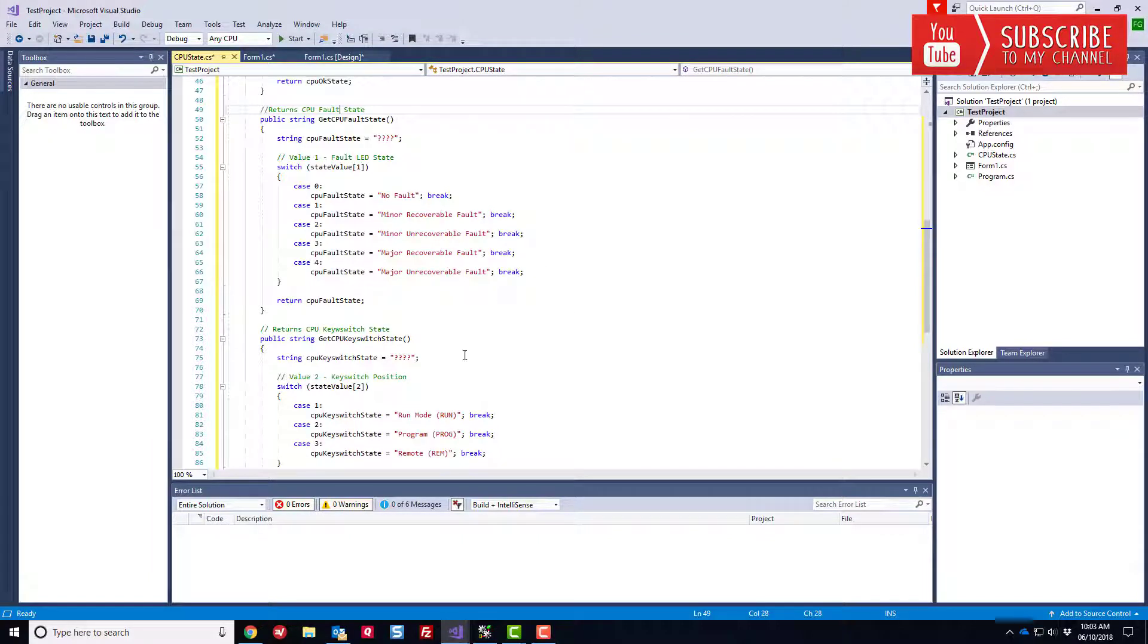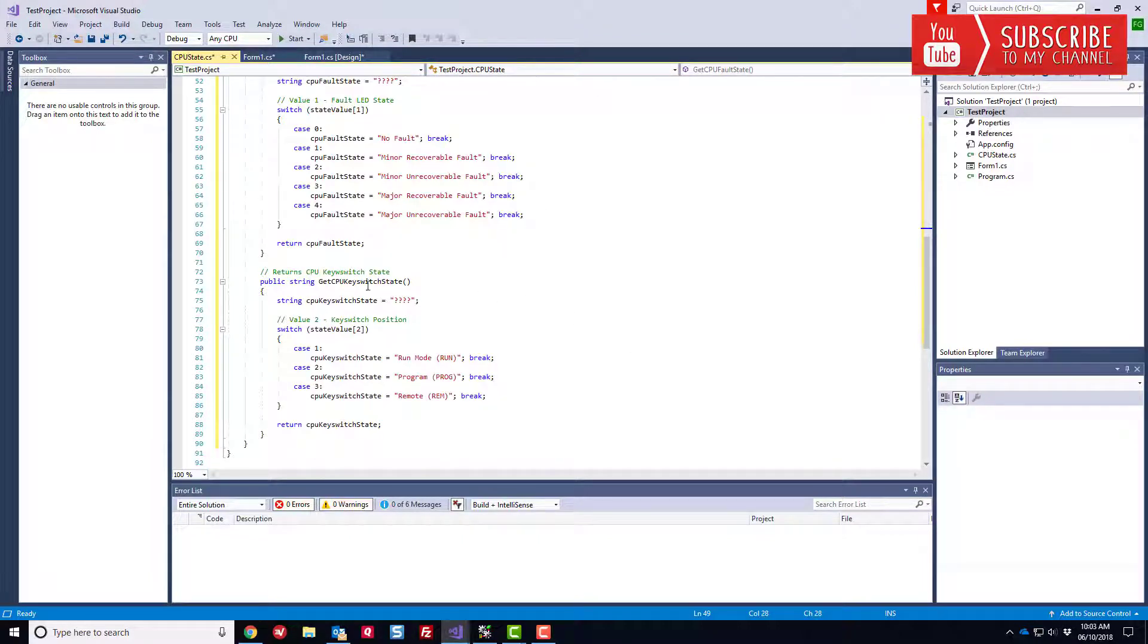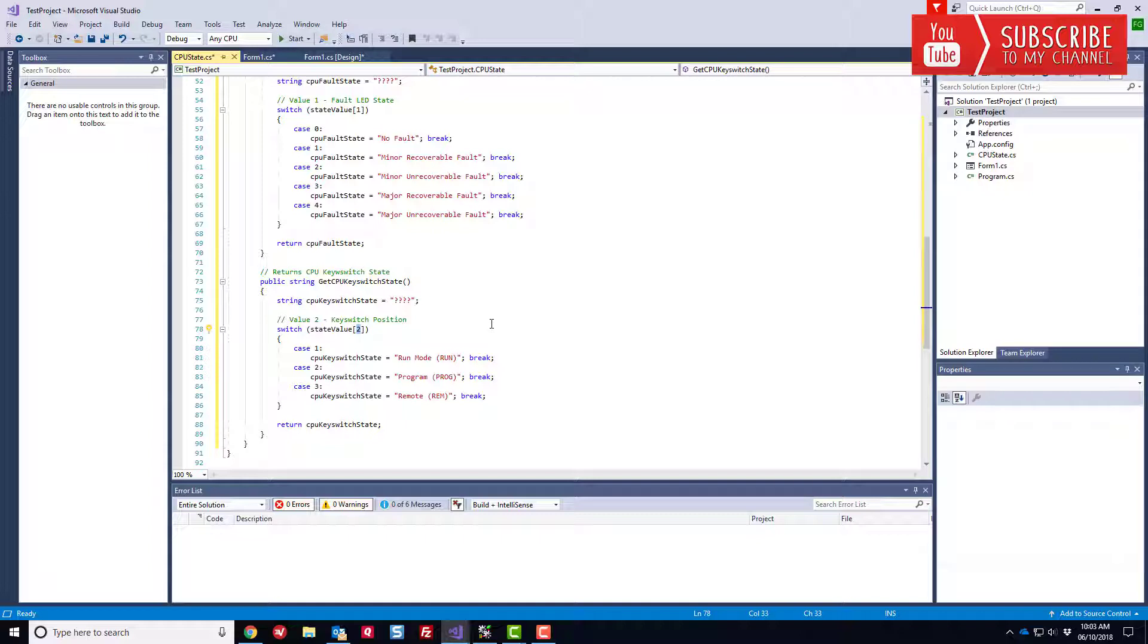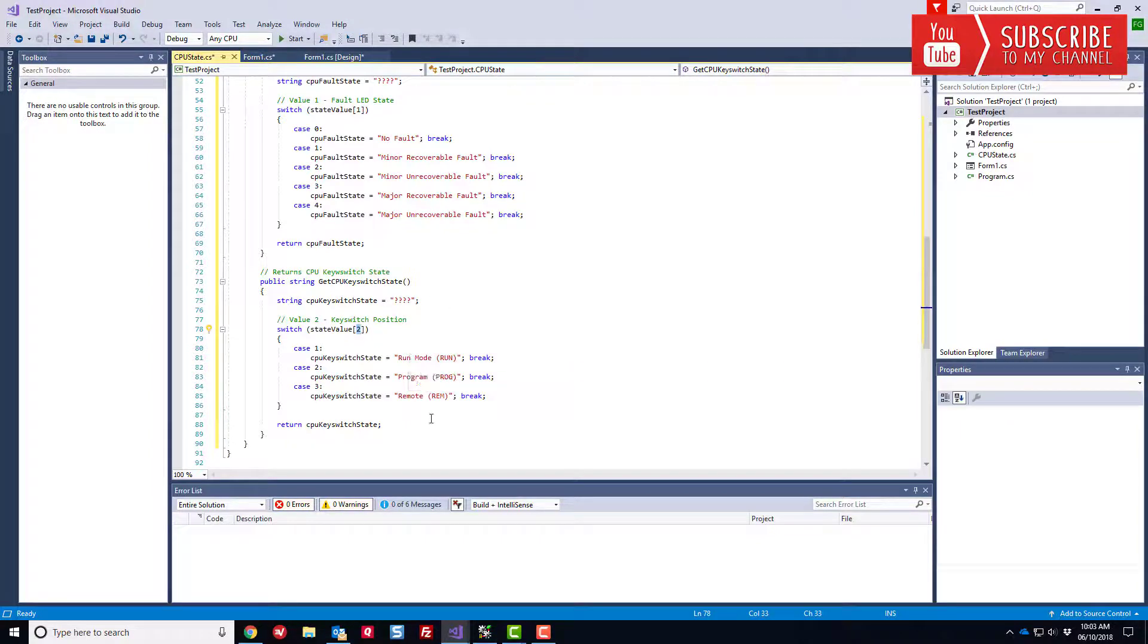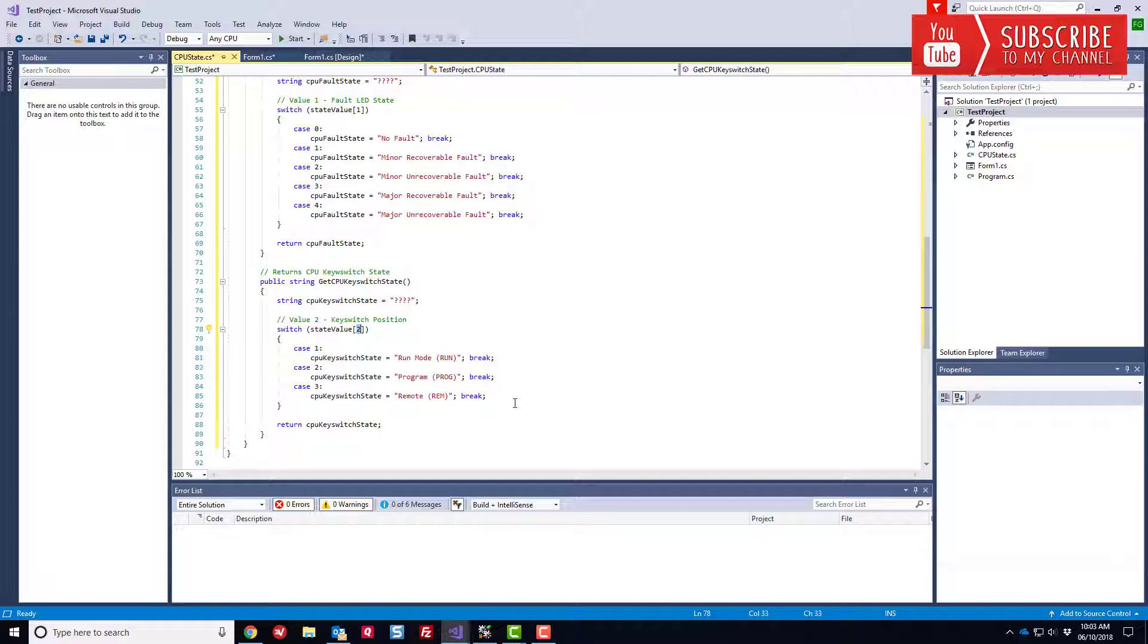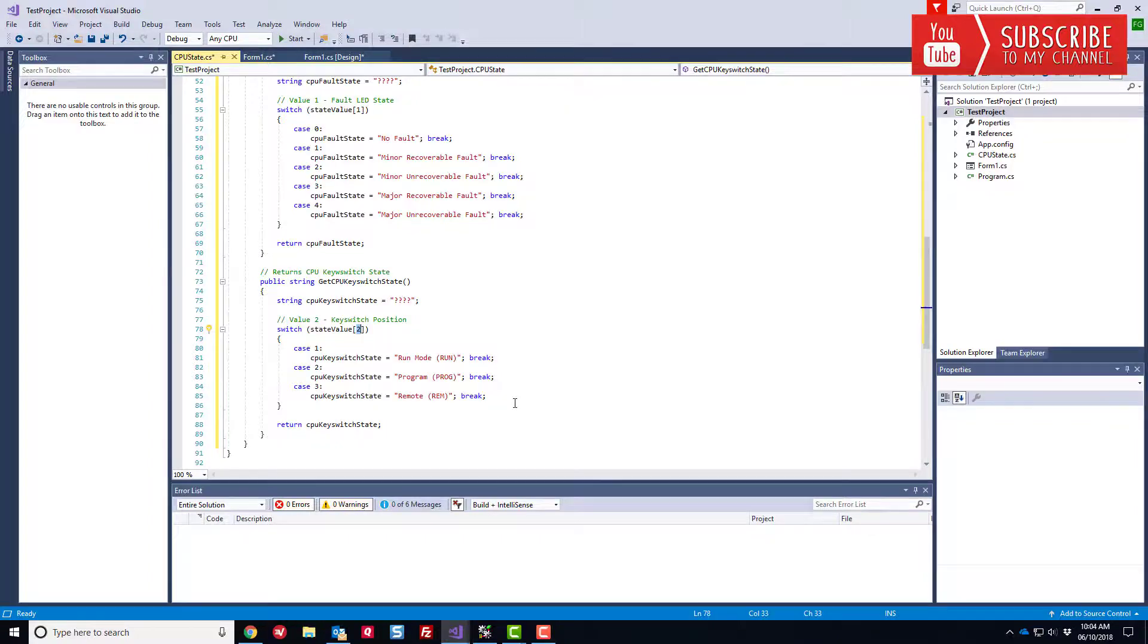And then finally, the CPU key switch state here. Again, same setup. We're using the array index two into the state value that's being passed into this object when it's first instantiated. And then we're going to test case one, two and three. That corresponds to run mode, program mode and remote run mode, respectively. So that's how we're going to go about handling some of the parsing and some of the heavy lifting associated with sorting out what was actually returned from our in-gear call to read the CPU state values.